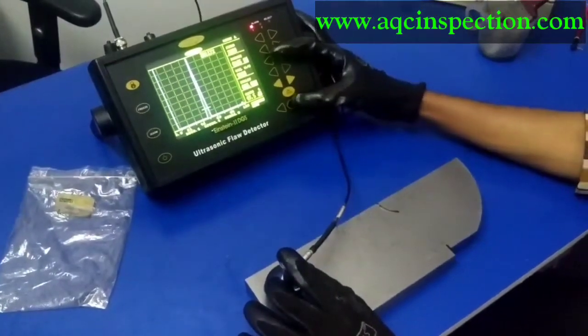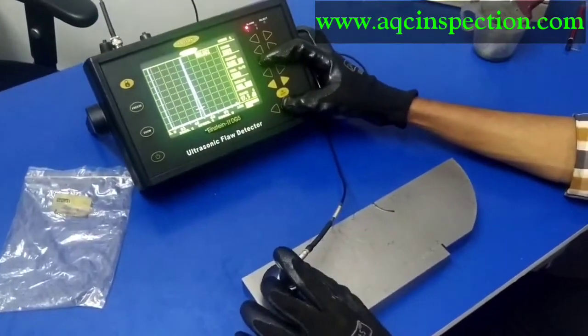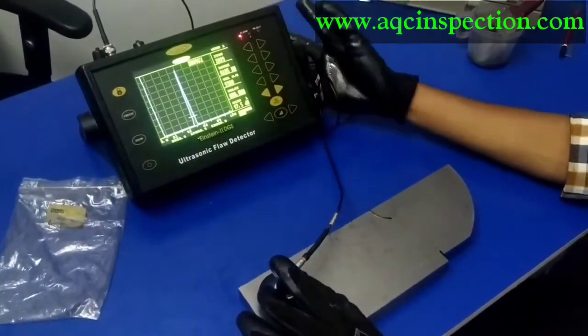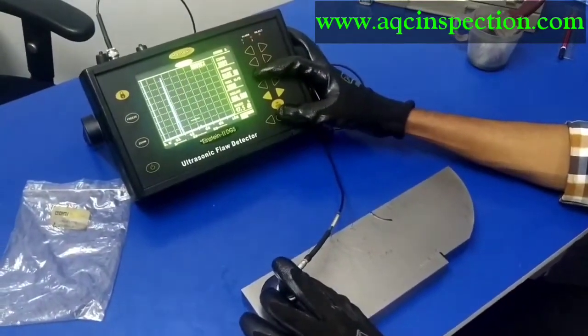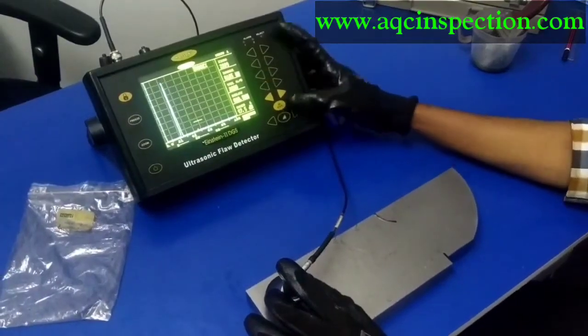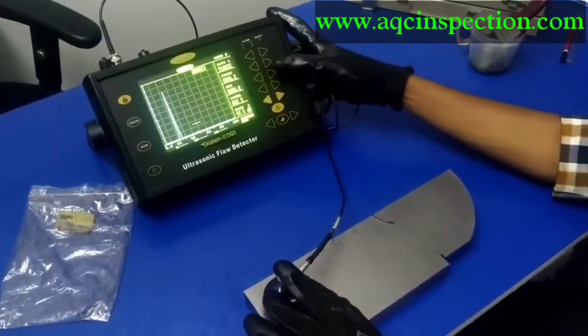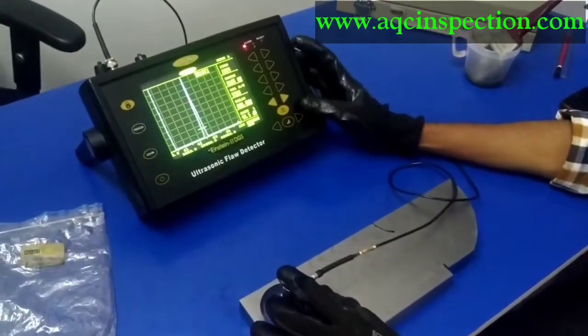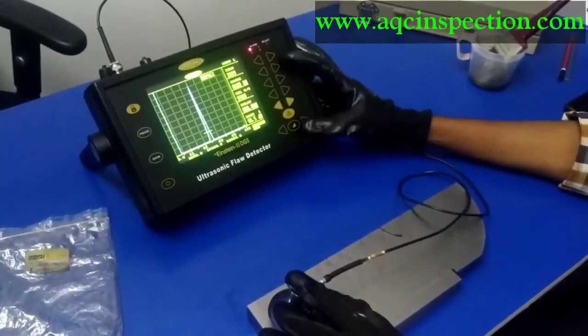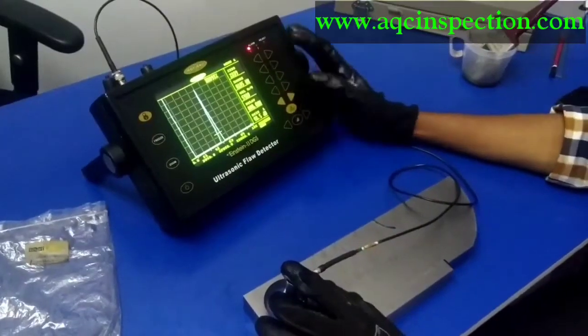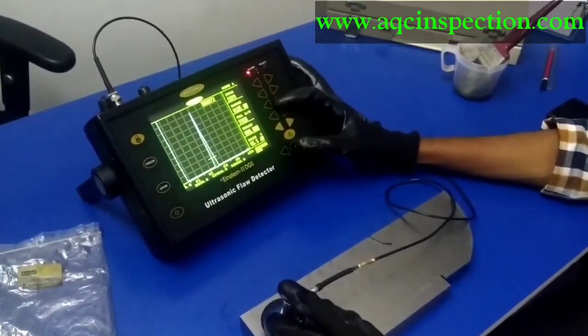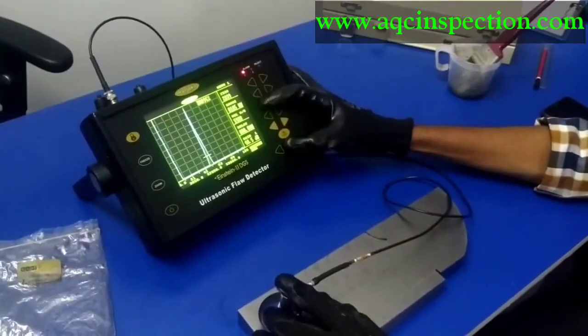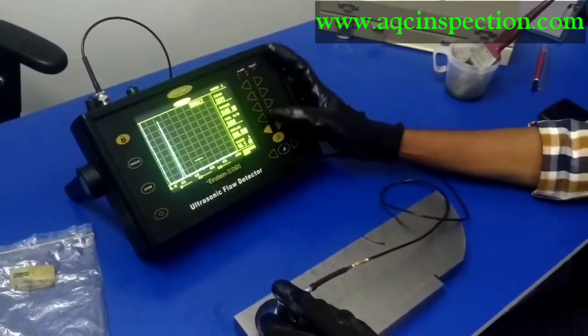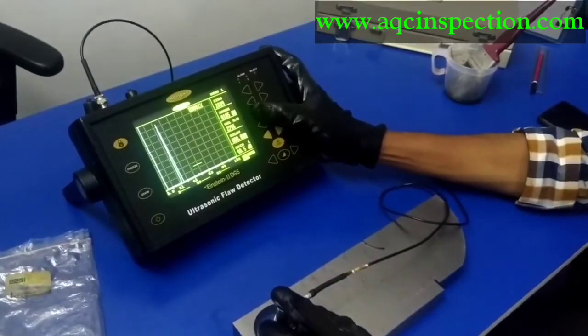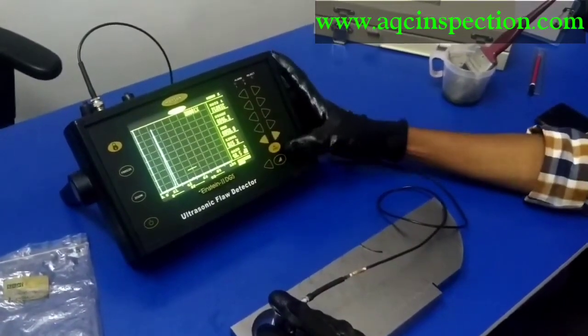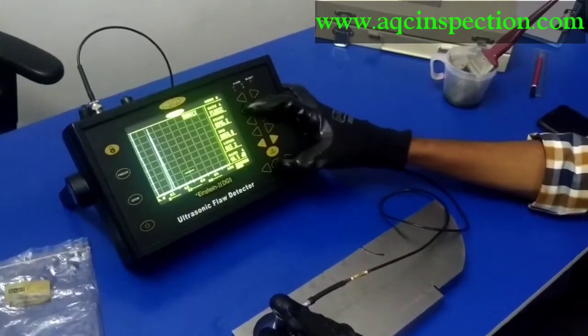Okay, right now I'm going to calibrate for the velocity of the plexiglass. So I have to change my velocity to the plastic velocity. It's almost around 2800 meters per second. Right now I am going to do the velocity calibration for the plexiglass, which is in the V1 block. We know the dimension has 23 mm thickness, so I am going to be adjusting the velocity for the plastic, which is almost 2800 meters per second. Let me move my gate a little bit to the front.